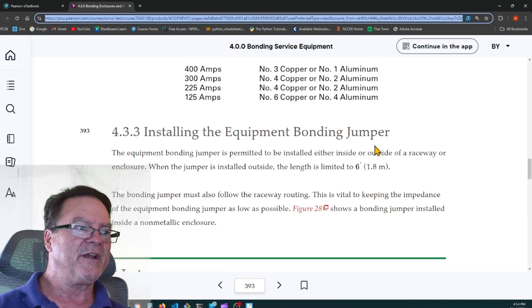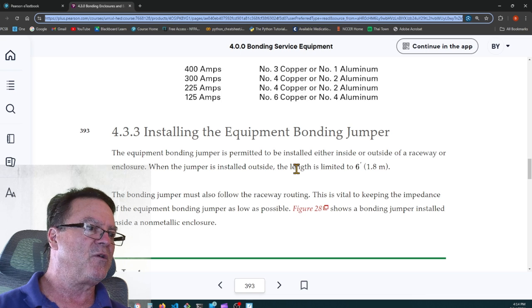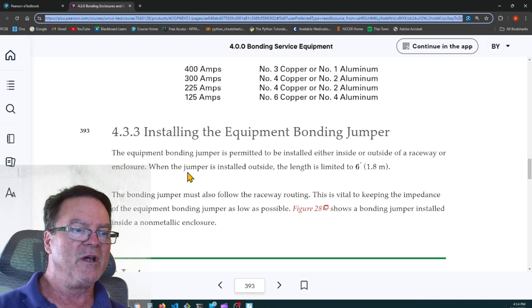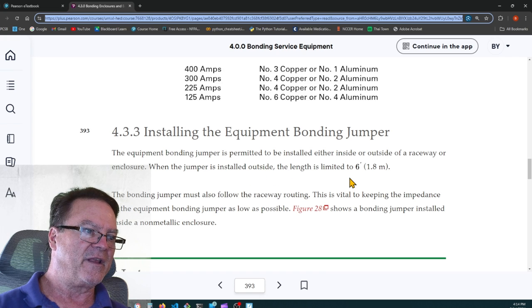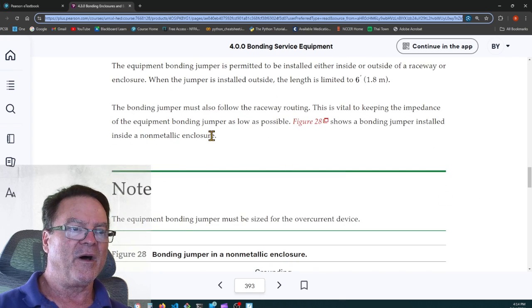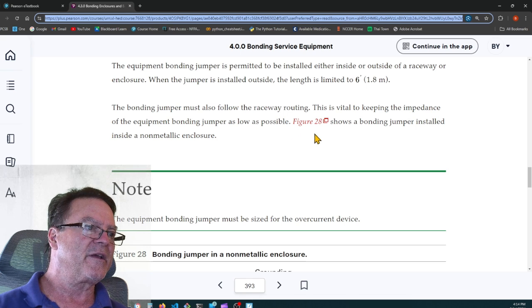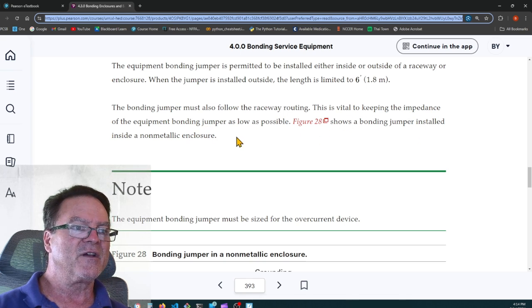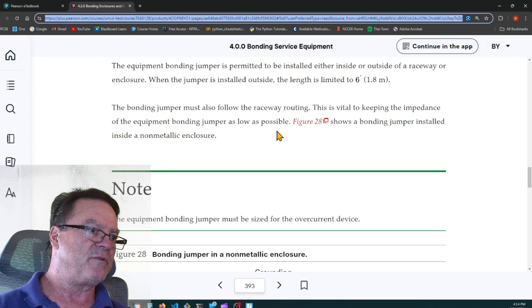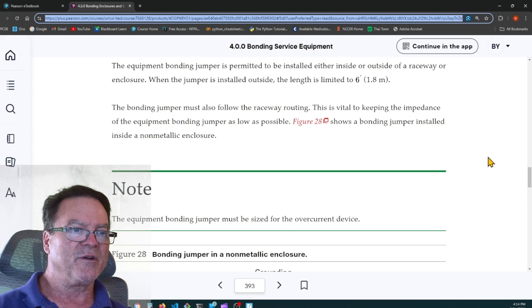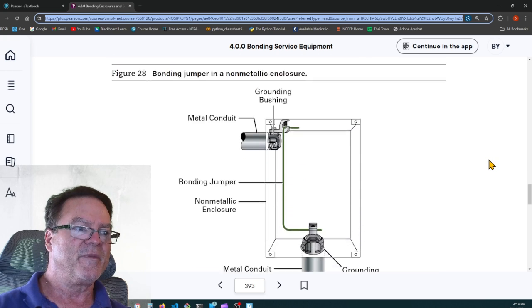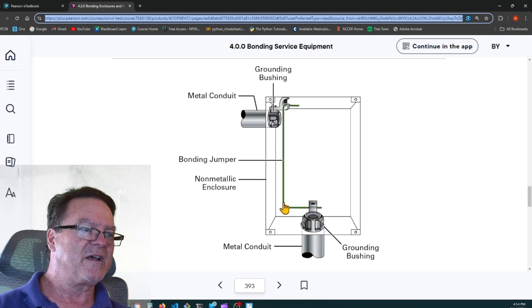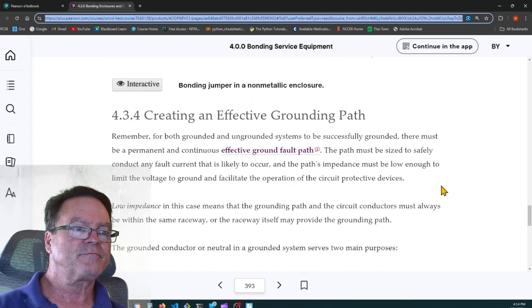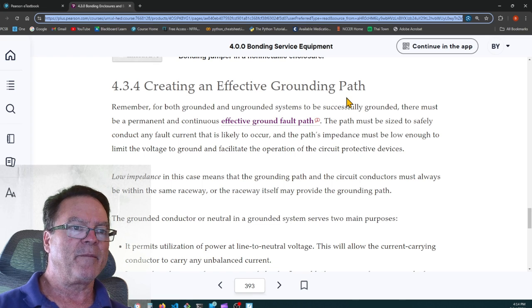4.3.3, installing the equipment bonding jumper. The equipment bonding jumper is permitted to be installed either inside or outside of a raceway or enclosure. When the jumper is installed outside, the length is limited to 6 feet. The bonding jumper must also follow the raceway routing. This is vital to keeping the impedance of the equipment bonding jumper as low as possible. Figure 28 shows a bonding jumper installed inside a non-metallic enclosure. So here's a bonding jumper inside a non-metallic enclosure. It goes from one grounding bushing on a metal pipe to another grounding bushing on a metal pipe, creating an effective grounding path.